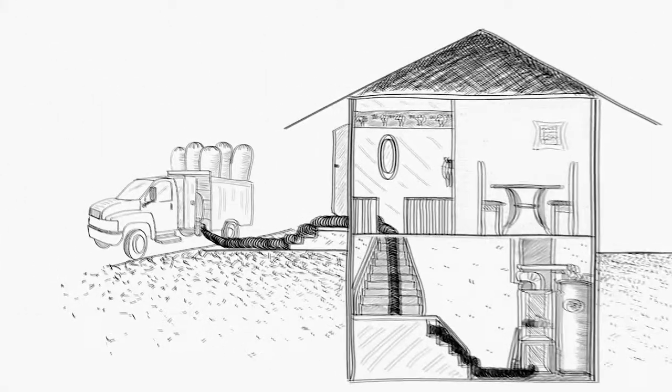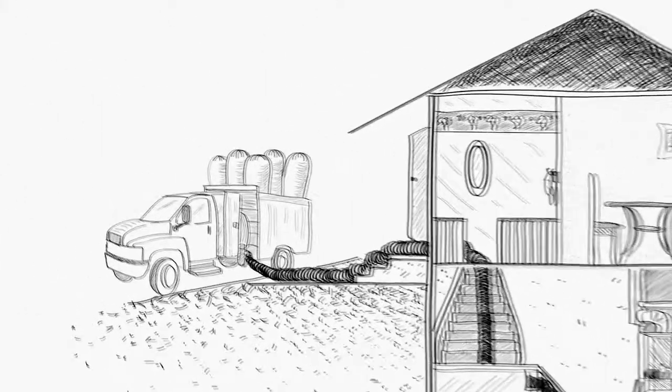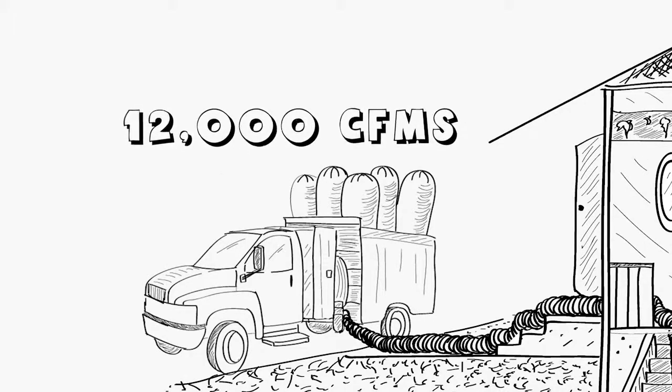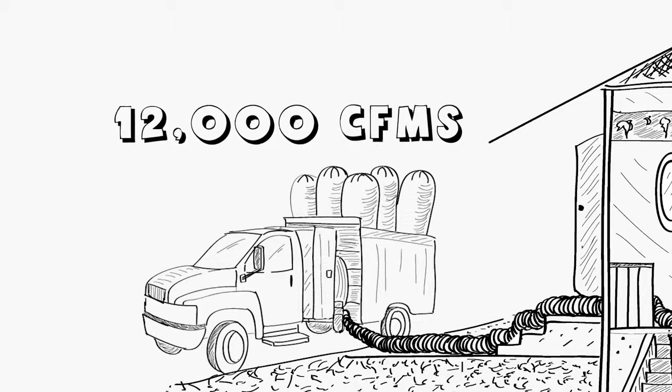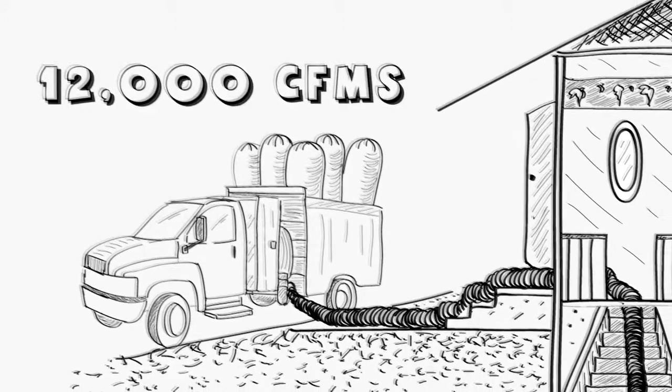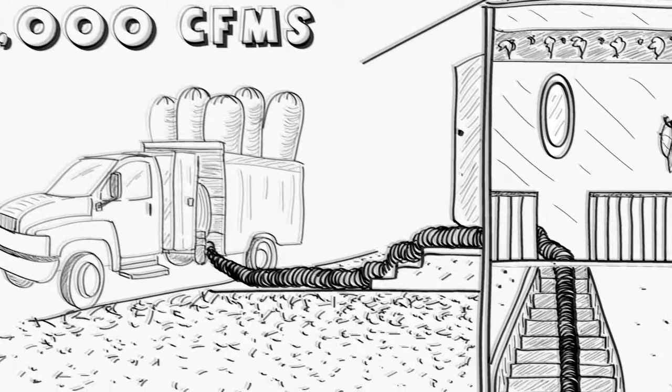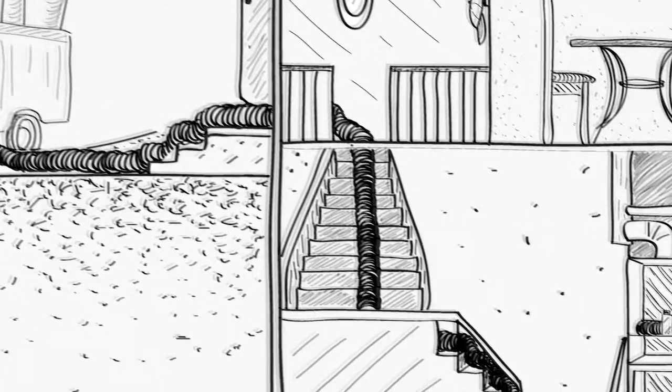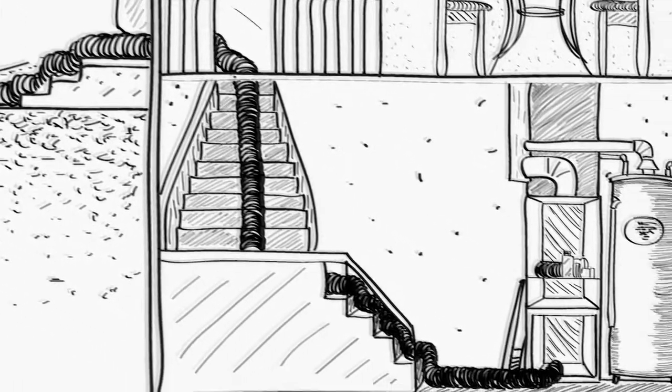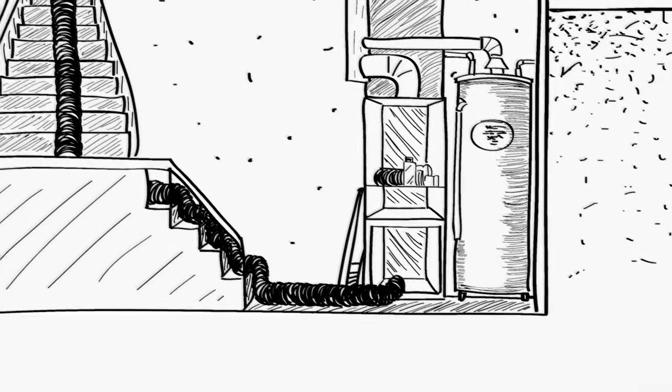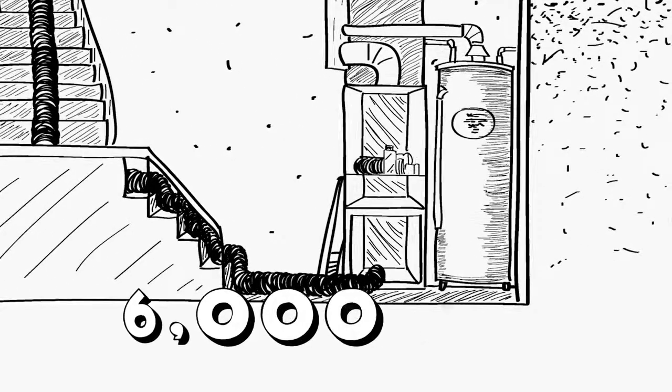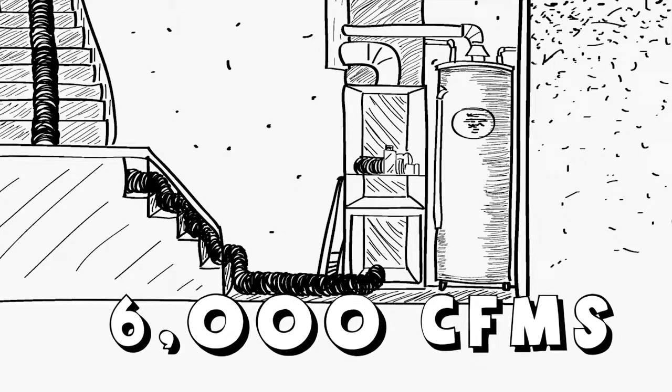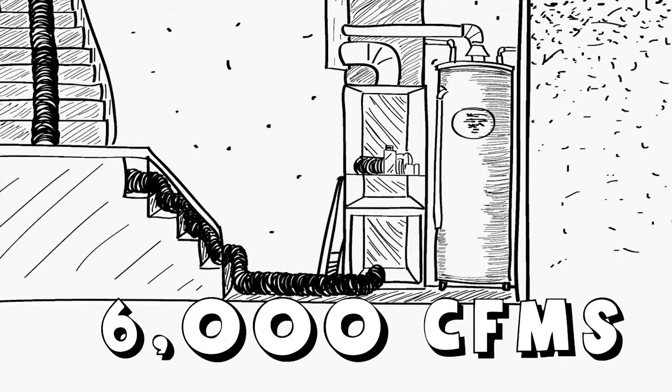Most duct trucks have around 12,000 CFMs of suction which is very powerful, but the drawback is a lot of this suction is lost in the long hoses to get from the street into the house, meaning that the suction at the furnace is probably closer to 6,000 CFMs at the hookup point. Still a lot of suction and more than enough to do a great job.